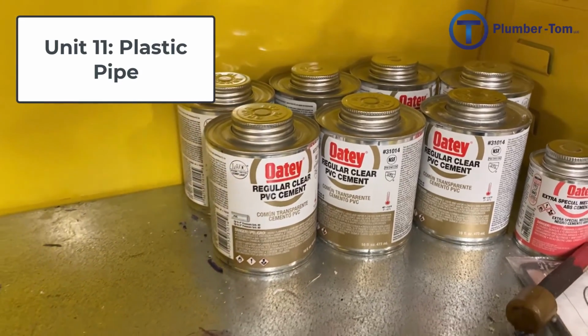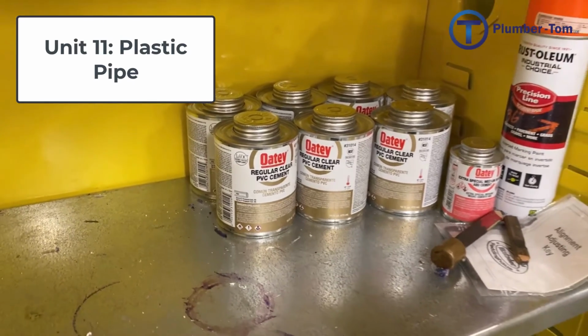PVC pipes are glued together, or they call that solvent weld. So you want to make sure that you have the right glue. For example, PVC and CPVC do have a different glue. They have a different chemical makeup. So we need something different to help adhere those pipes and fittings together. You want to make sure you're using the right stuff. Similarly, you don't want to be using ABS glue on PVC pipe. It's a totally different chemical. It's a different plastic. You have to stick with ABS glue for ABS pipe.